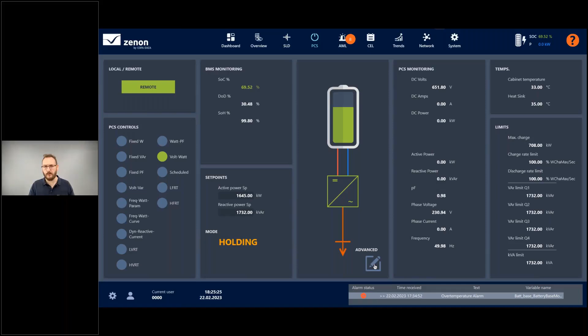As I mentioned, battery banks can be extended quite rapidly due to their function. So whether an industrial customer needs to add more capacity to the bank, or similar situations, we would need to change some parameters of the inverter to cope with the additional capacity. This can be done via such an application, where here we are accessing the inverter itself.